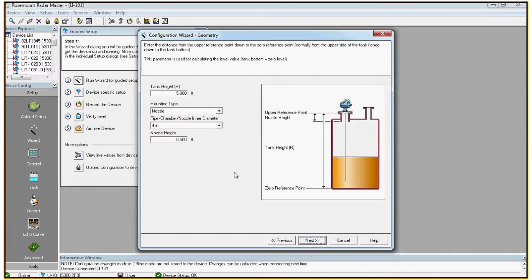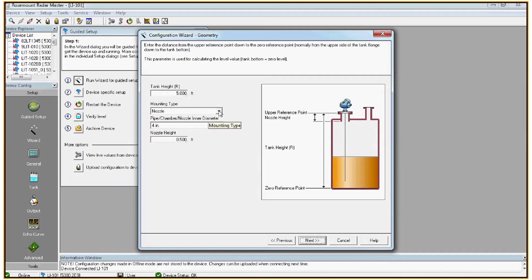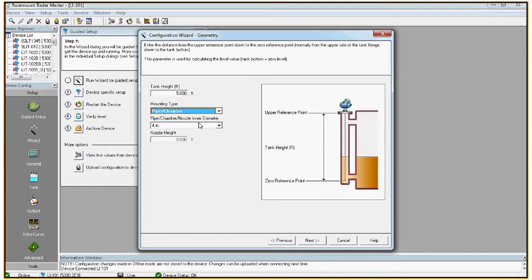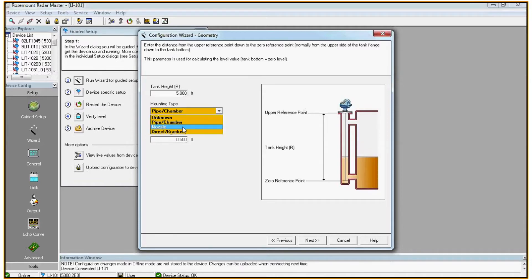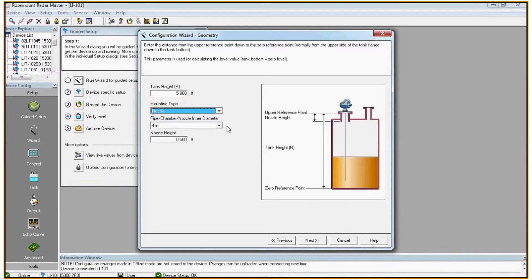Here we can configure the tank height. Tank height is always measured from the bottom of the flange to the bottom of the tank or what you're calling zero in the tank, and you also configure the mounting type. For this example I will use a nozzle style. Again on this screen, if you change the mounting type, the picture will update to give you a reference. It's important that you also configure the nozzle diameter and the nozzle height.